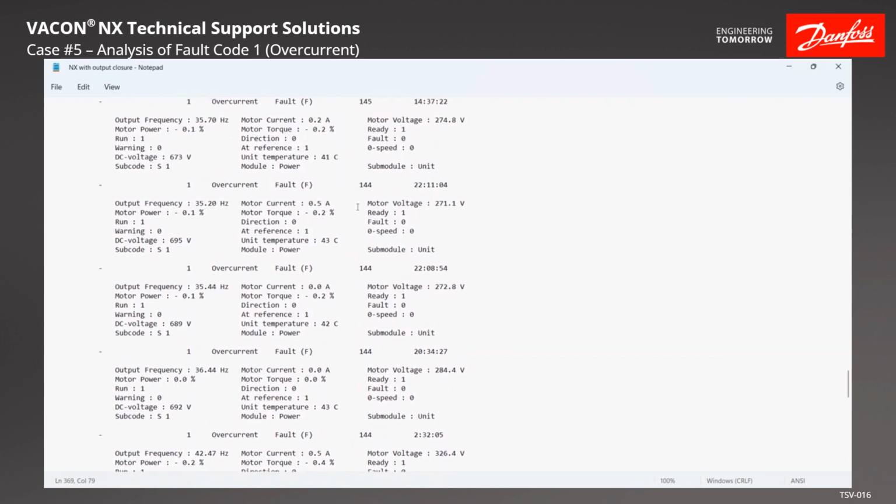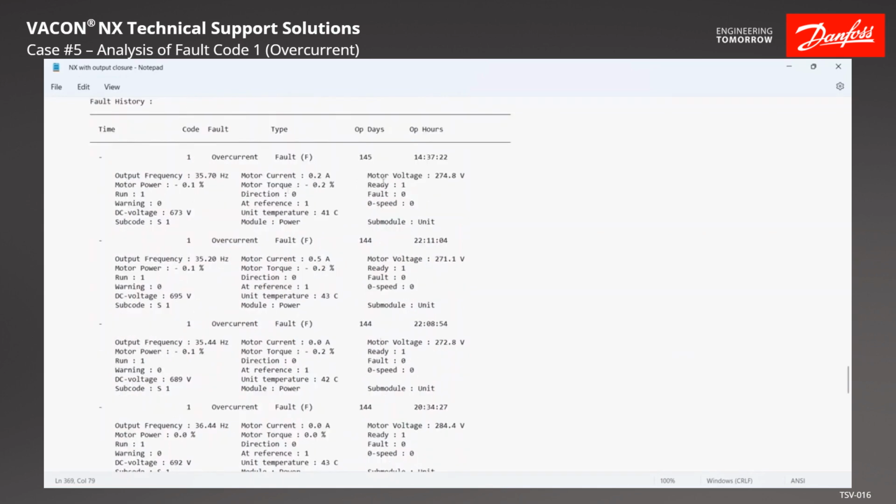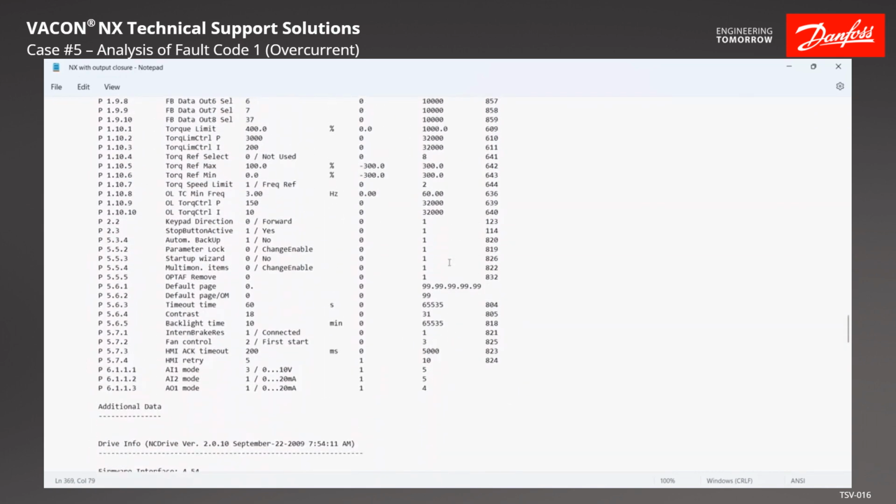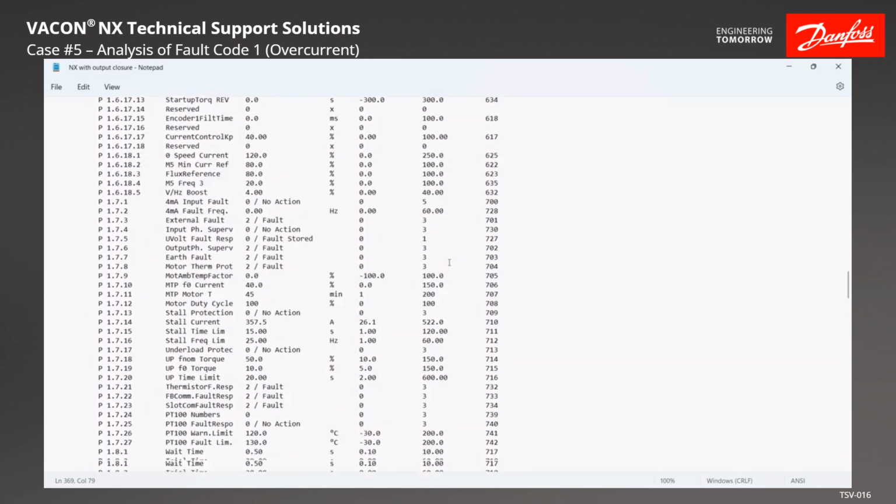So it's probably not a disconnect, because somebody's not going to sit there and open and close a disconnect. They might do that once. Could be a contactor. You do have to take a look and say, are there any contactors out there that we can possibly bypass, and then wait a couple days and see if these faults stop happening. In this circumstance, it was neither one of those. It was not a contactor or a disconnect.